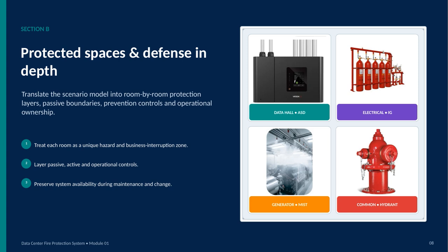The second principle is layering. Passive boundaries, active suppression or detection systems, and operational controls should reinforce one another, so that a weakness in one layer does not become a total loss of protection. Finally, protection has to remain effective during maintenance and system changes. Availability is not just a design goal. It must be preserved through clear operational ownership, controlled work practices, and coordination whenever systems are isolated, modified, or returned to service.